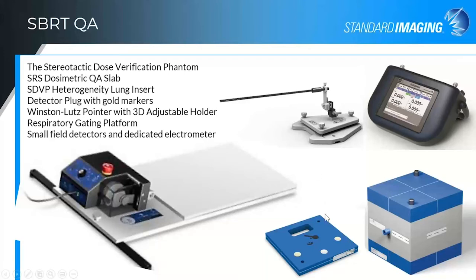And I would like to suggest that our stereotactic dose verification Phantom, here you can see it with the heterogeneity slabs, is an ideal Phantom solution. We have the respiratory gating platform for motion management. We have our Winston Lutz pointer with 3D micrometer and tools such as our Supermax, and again with detectors like the A26 diodes or our W1 or W2 scintillator are fantastic tools for that SBRT program.